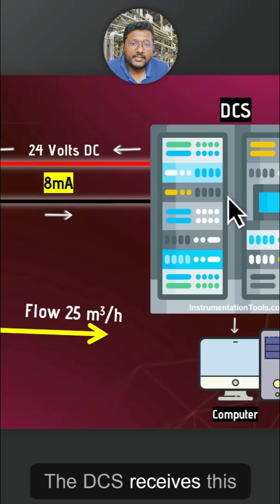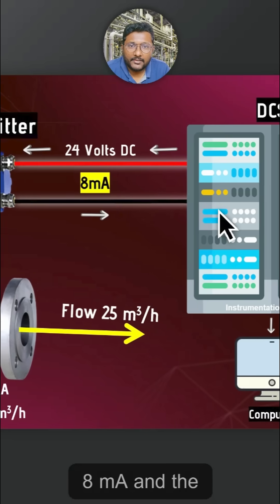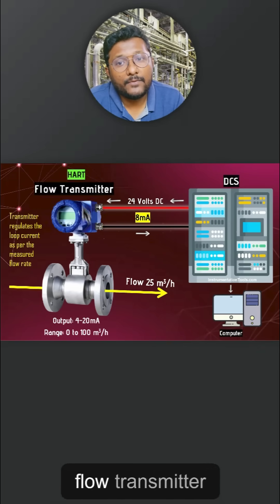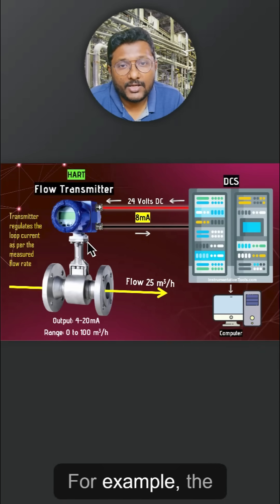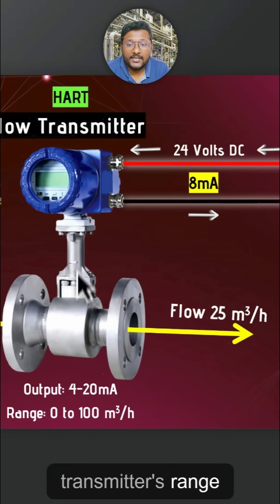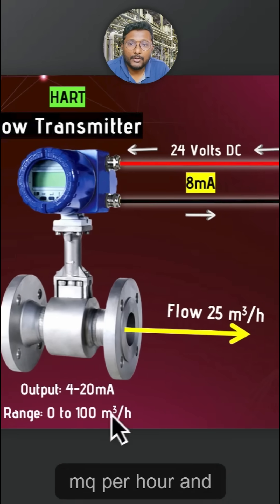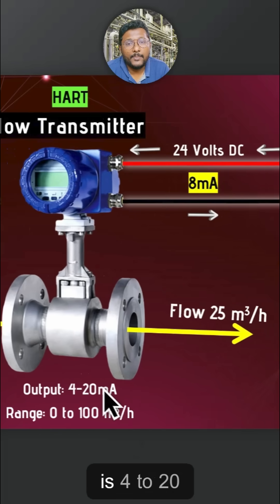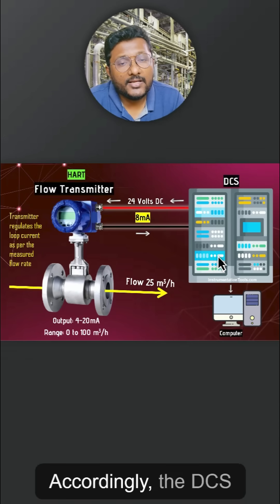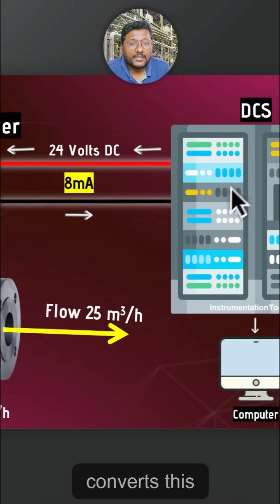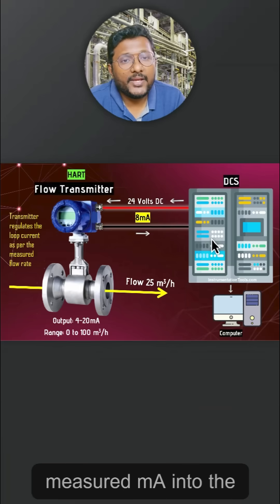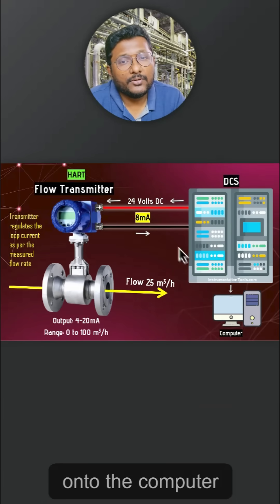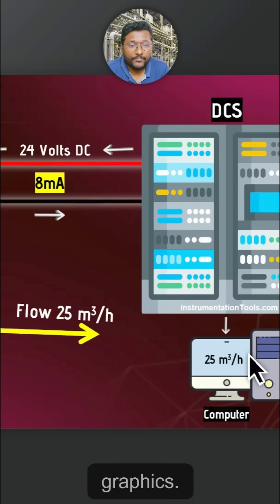The DCS receives this 8 mA and, since it is already configured with the flow transmitter details — for example, the transmitter range is 0 to 100 m³ per hour with an equivalent signal of 4 to 20 mA — the DCS converts the measured mA into the equivalent flow rate and displays it on the computer graphics.